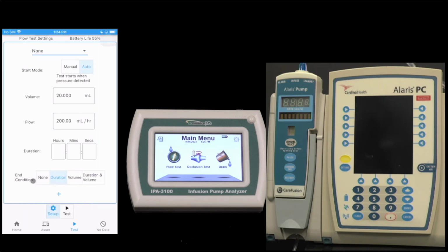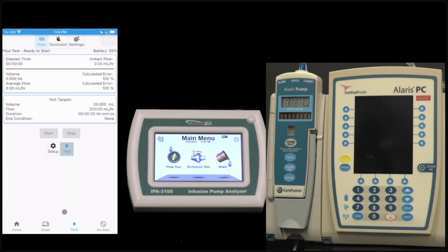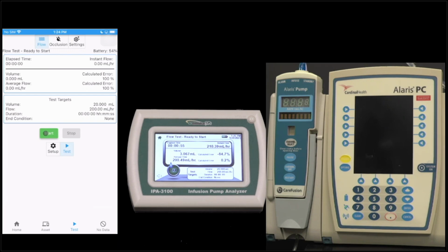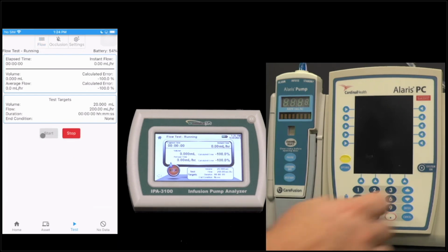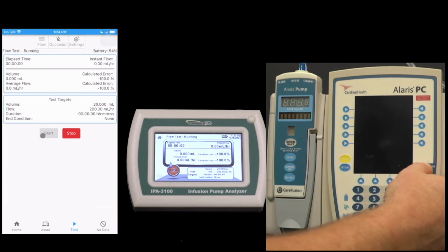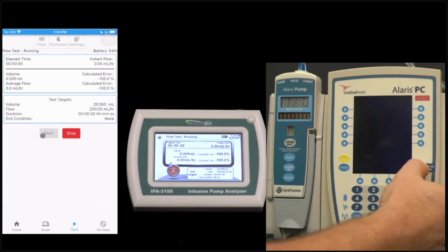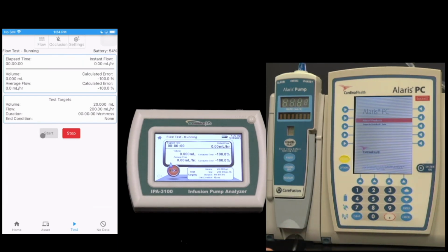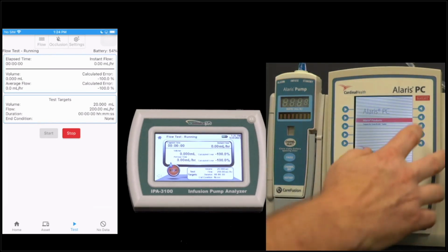So we want to end — I'm just going to manually end. Then we go into the test, and the test has been sent, the configuration has been sent. We can say start, and then we can go over to our pump. Just like before, the test is ready to go, and all I have to do is get the pump configured and run the flow through the device, and it'll give me my measurement.